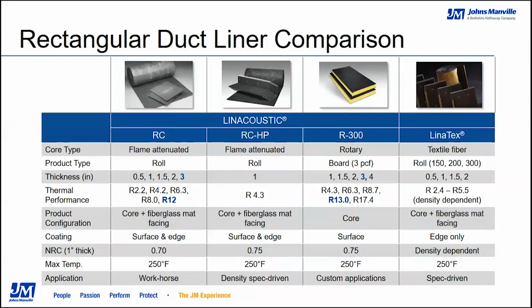Then the last product we offer is our LINATEX product, and JM is really the only manufacturer left in the market producing a textile fiber product. It's a long fiberglass product, density dependent, so you've got a 1.5 pound, 2 pound, or 3 pound product. As you increase thickness and density, you need to make sure you have the right thickness and density combination to hit the needed R value to reach the code you're trying to meet.